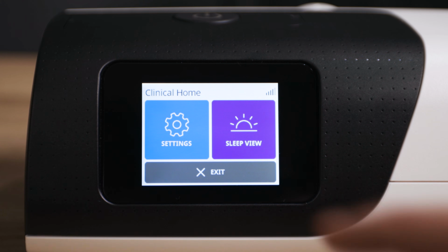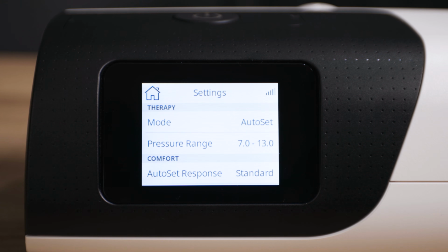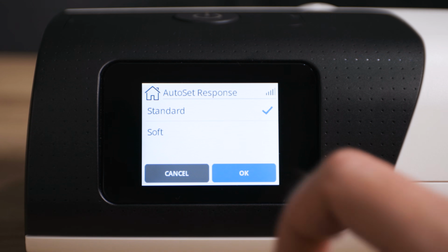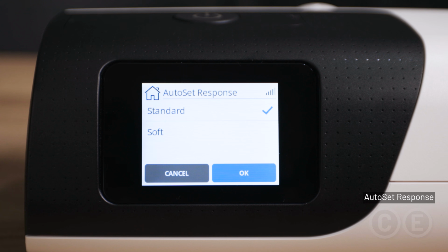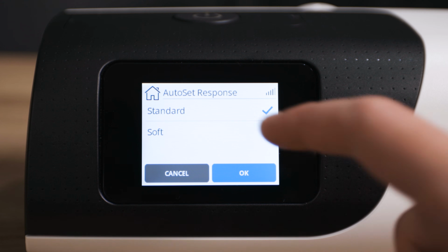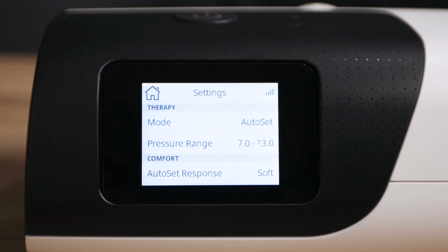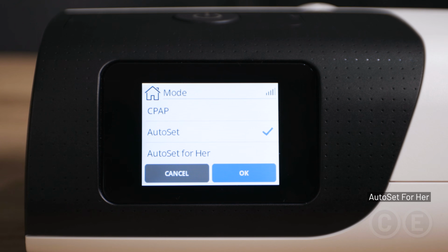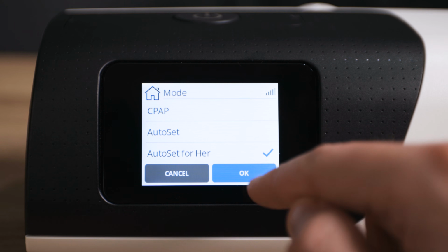That being said, within your AutoSet mode, you are able to choose a soft or standard response. Soft response will mean the device uses gentler pressure increases and decreases, whereas in standard mode, the unit will reach the intended pressure faster, but you may notice the pressure changes a little stronger. And as I mentioned before, the AutoSet for Her mode is now simply a feature within the mode settings, as opposed to it being a standalone device.